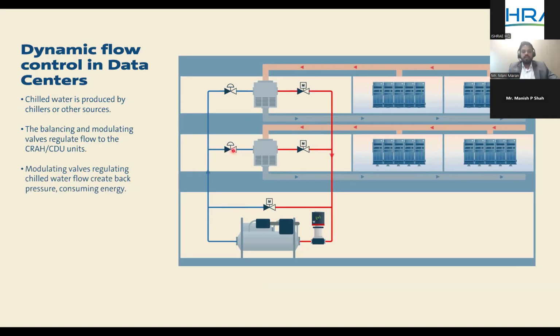So what is the challenge that we see here, and what do we need to overcome from the design that we propose? When we do balancing, balancing is of course a critical parameter, as I said, but it comes with cost. When we do balancing, the friction created by this valve is added as pump head, and every time the pump has to overcome that friction, it consumes energy, which is like driving a car by putting on the brake and accelerator at the same time. Similarly, when there is a change in the flow, this valve has to further modulate. When the valve modulates, it creates further friction, and that friction always has to be compensated by the pump by consuming more power.